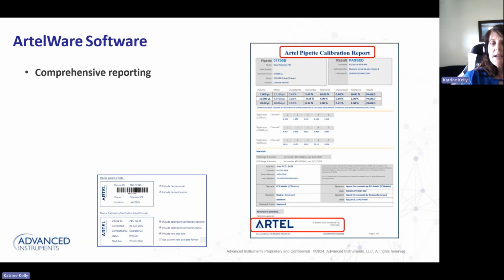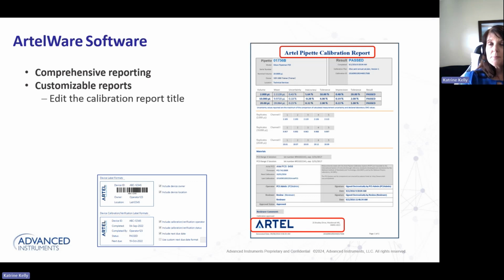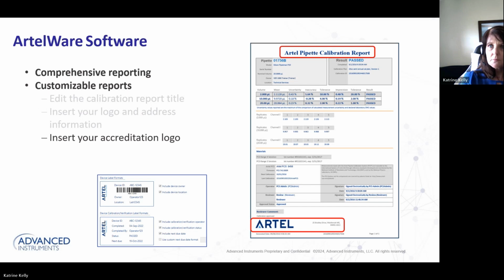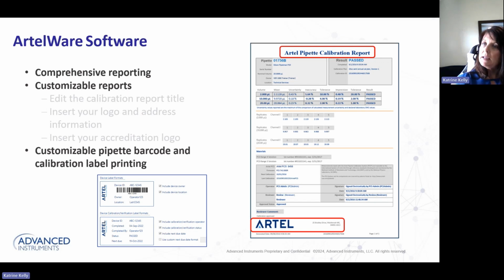So the software comes with comprehensive reporting. To the right is an example of a pipette calibration report. You can customize those reports to edit the calibration report title and the footer. You can insert your own logo and address information in the footer. You can also insert your accreditation logo if you are accredited. And you can customize the barcode and calibration labels. The pipette barcode ID label can be customized to include or exclude the owner and location. And the calibration label can be customized to include or exclude the operator, the status, or the next due date. And those date fields, the format can also be changed.